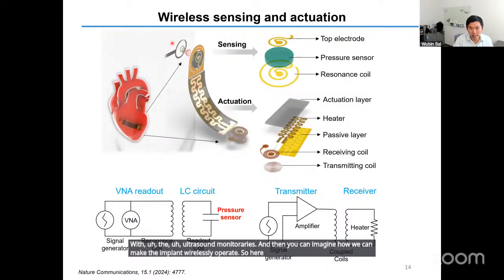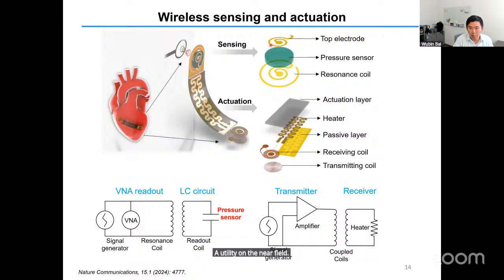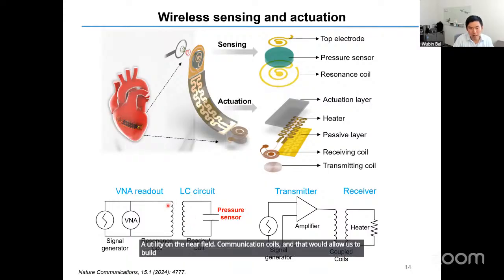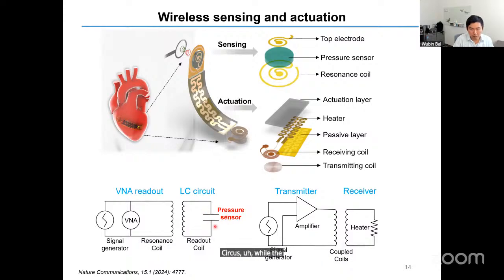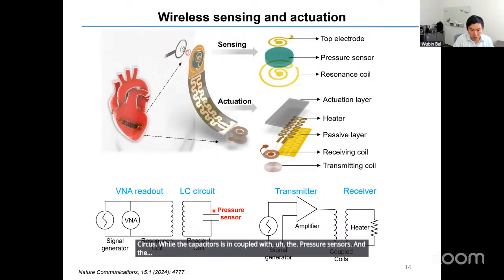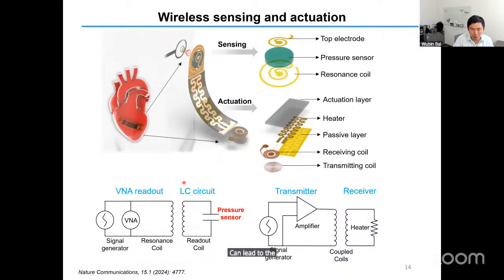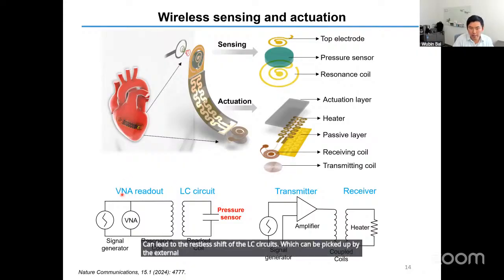So here we provide a design utilizing near field communication coils, and that would allow us to build LC circuits, where the capacitor is coupled with the pressure sensors, and the capacitive change, which is a result of the external pressure change, can lead to the resonance shift of the LC circuits, which can be picked up by the external VNA readout.